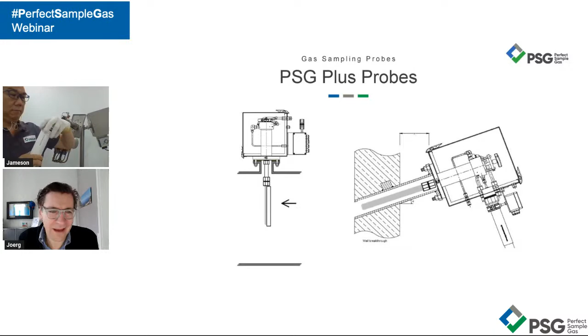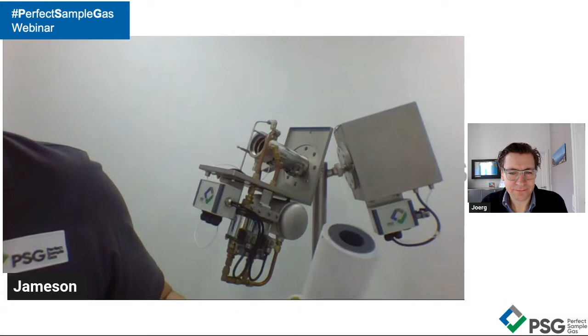Yeah, okay. That's a great description, James, and it's nice to show the filter. I think we also have a special slide for this. And it's great to see how easy it is to really change the inside of it. Let me put you on the bigger screen again. Yeah, the filter is designed in such a way that we do not need any tools, all right? You only need a glove because it's really hot, 180 degrees. And after removing the filter, it is important, I repeat why it is important, that the filter element is sized against the head space. The reason is response time. Also because of calibration, we do not want all the calibration gases rushing out into the process. You see? And it's very unfriendly in terms of the environment. So this is why.